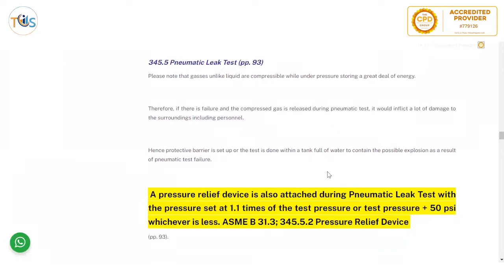Hence, a protective barrier is set up, or the test is done with a tank full of water to contain the possible explosion as a result of pneumatic test failure. A pressure relief device is also attached during pneumatic test and leak test, with the pressure at 1.1 times the test pressure. Remember, this is 1.1 times the test pressure, or test pressure plus 50 psi, whichever is less.